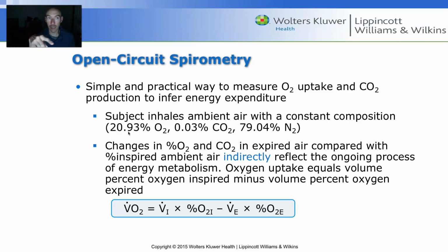So as you'll see next week in our first lab, before we ever do a test with our metabolic cart, we have to calibrate the cart and put in barometric pressure, temperature, humidity, so the computer will know how those variables affect the concentration of gases coming in. So then as we expire, we're sort of comparing accurate information, right? So we do have to calibrate the cart based upon those factors, okay? But in general, this is the percentage of the gases in the air around us, okay?